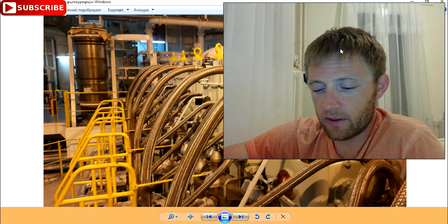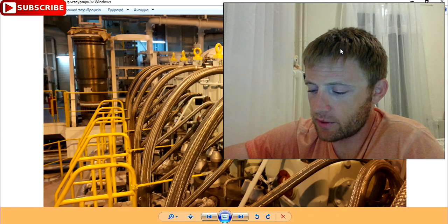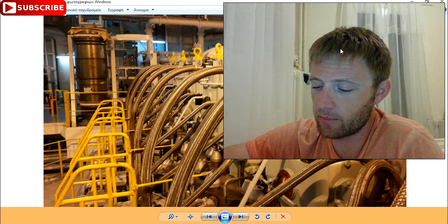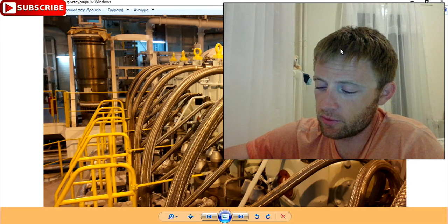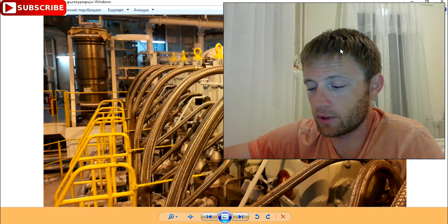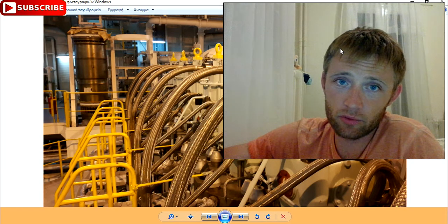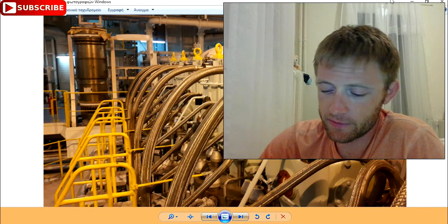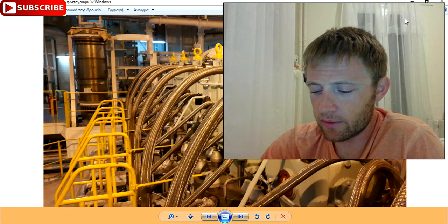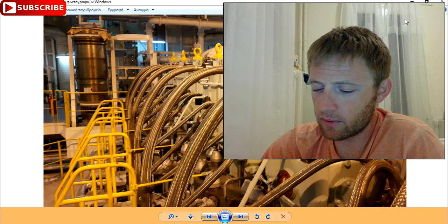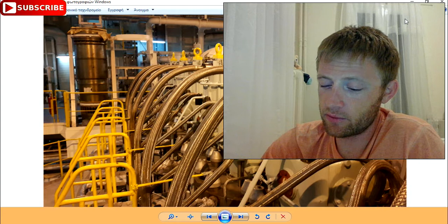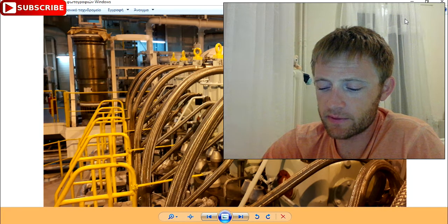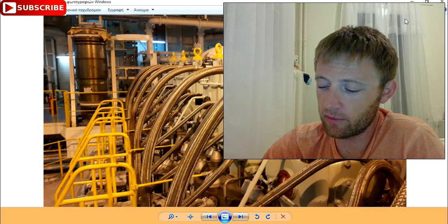Okay, five, when we discharge, we put two pumps working and one pump on standby. In small ships, you do not need to do this. For those who know, they will understand and they will refresh their knowledge. Okay. Number six. In the return of the oil tank, there are two safety valves. One safety valve is set at 6 bars and the other one at 12 bars.